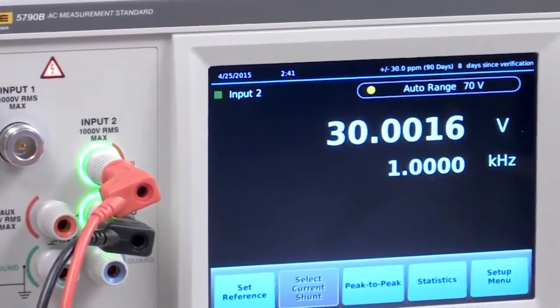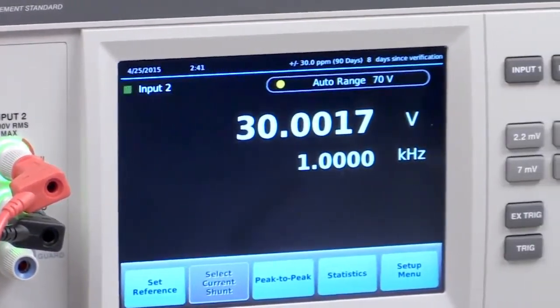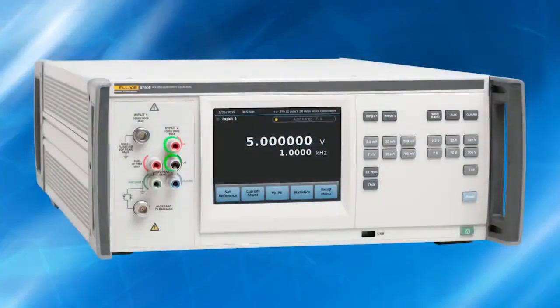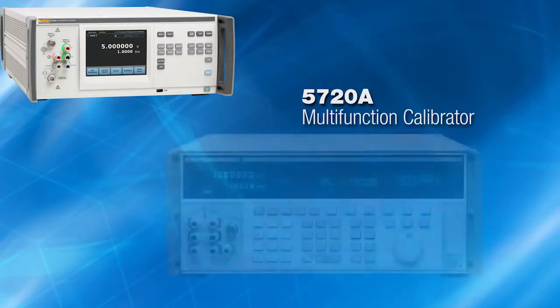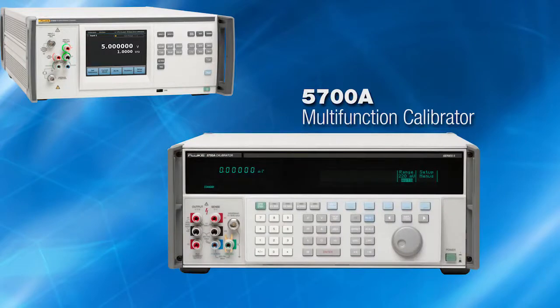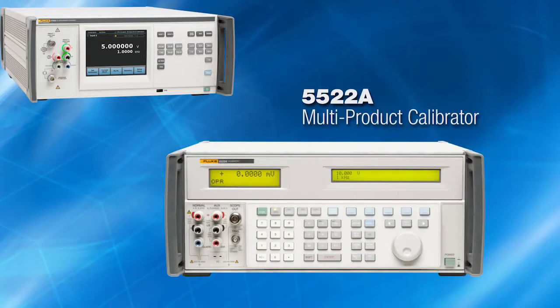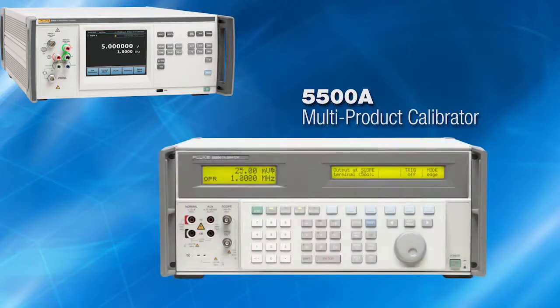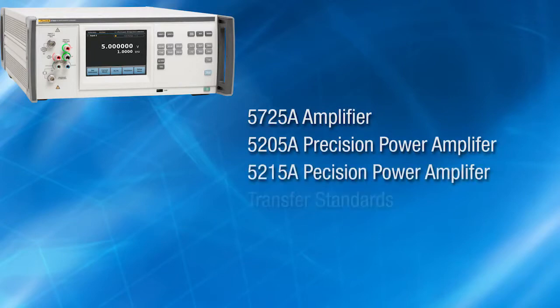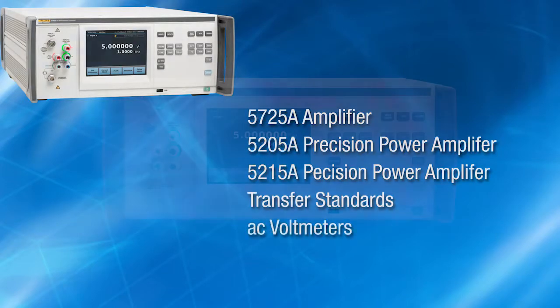It combines the accuracy you would expect from a thermal transfer standard with the ease of use of a digital multimeter. The 5790B is designed to meet the complete AC voltage and wideband verification requirements of the Fluke Calibration 5700 series multifunction calibrators, including the 5730A, the 5720A, and the 5700A. The 5500 series multi-product calibrators, including the 5522A, the 5502A, and the 5500A, plus other calibrators and amplifiers like the 5725A, the 5205A, the 5215A, and transfer standards and AC voltmeters.